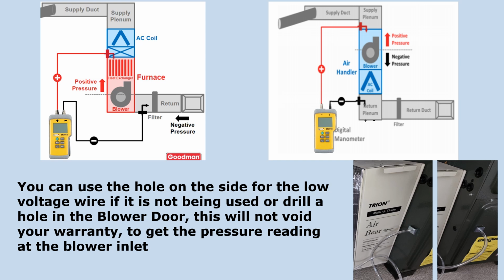And you want to make sure that you get it as best you can. Sometimes there are some weird applications and you might not get it perfectly into the airflow direction, but try to. And as you can see here, it shows that we're under the A coil and inside the cabinet, inside the filter. And that's where you always want to be, because again, remember, we're trying to measure the external static pressure, which means everything external to that furnace box.